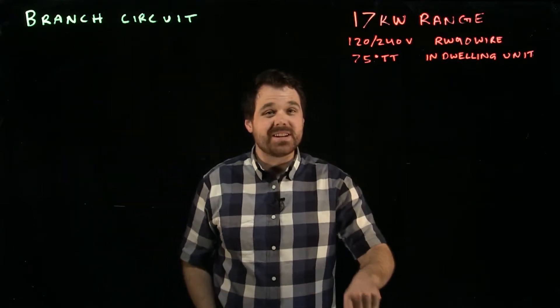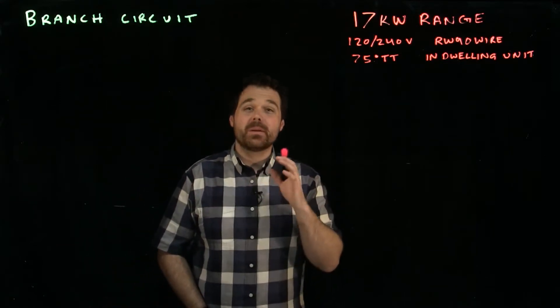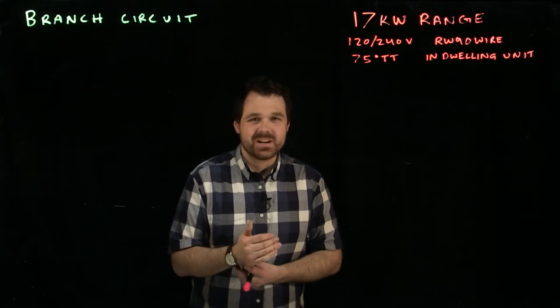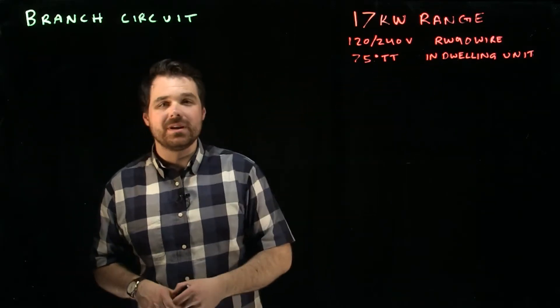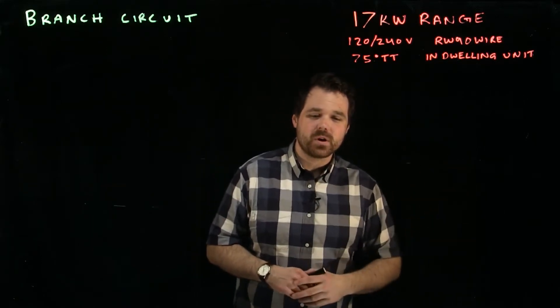So it's important to remember what the definition is, a branch circuit from Article 100 of the code. A branch circuit is from the final overcurrent device to the point of utilization. So in this case, from our breaker in our panel in a house, because we're in a dwelling unit, to the actual range itself. So we're sizing that wire and that overcurrent device.